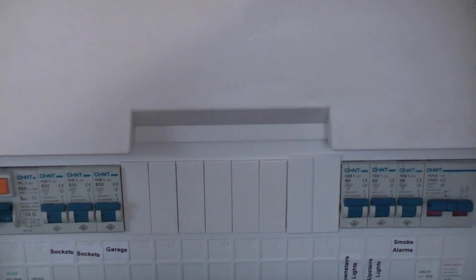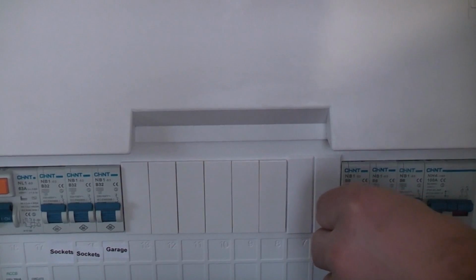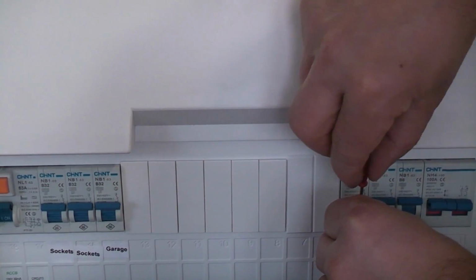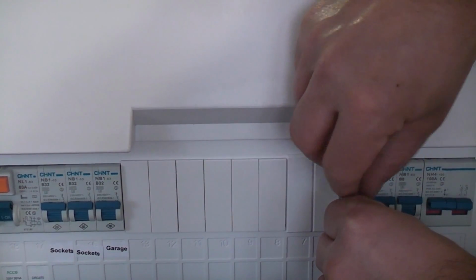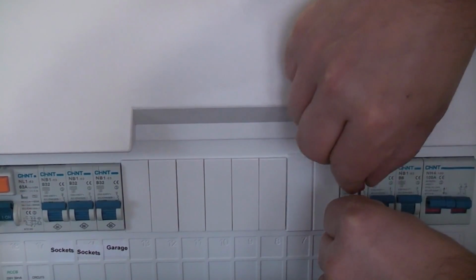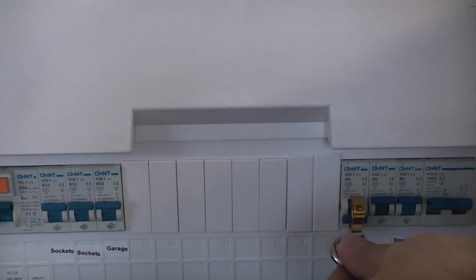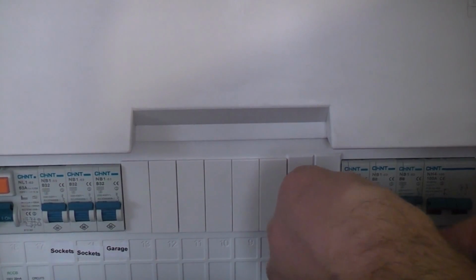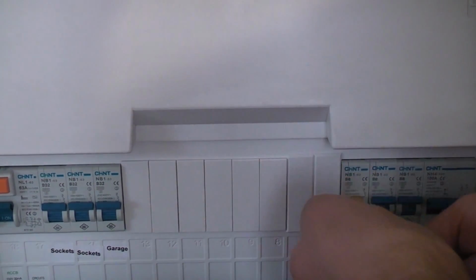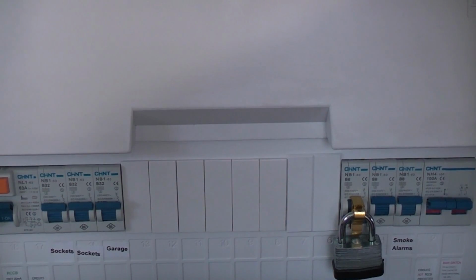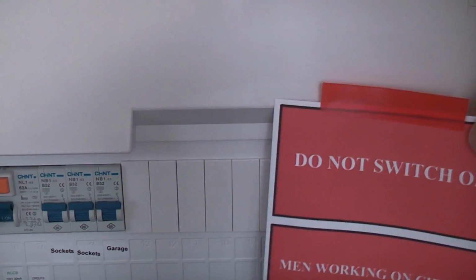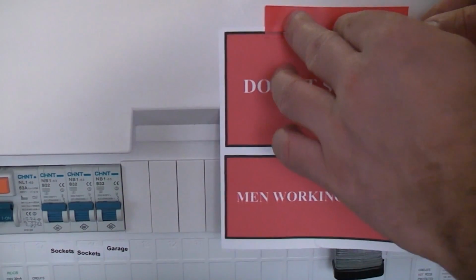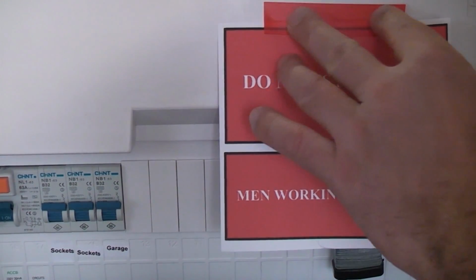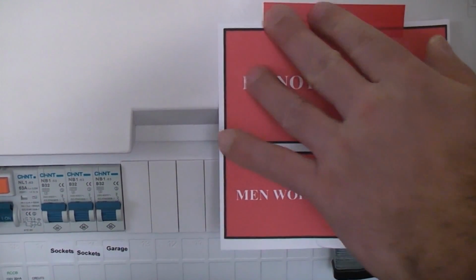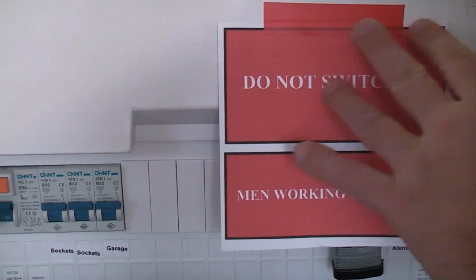So we're just going to isolate that switch. We can then lock off the MCB using a lock off. So I can now put the padlock through there and there is no chance of anybody switching that circuit back on whilst we are working on it. As an extra precaution, we're just going to put a label on there that says do not switch on. It's a good idea doing this if you live in a house where somebody may come in and switch the electricity on whilst you're working on it.